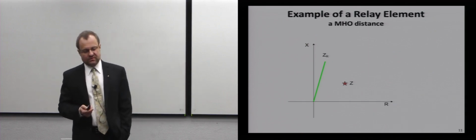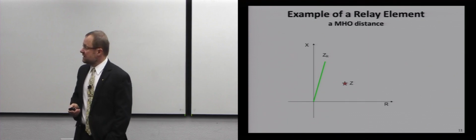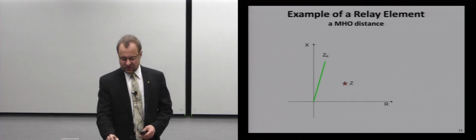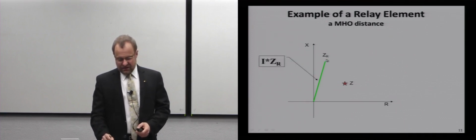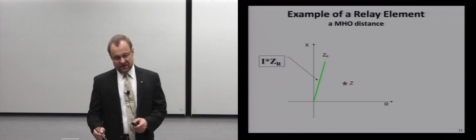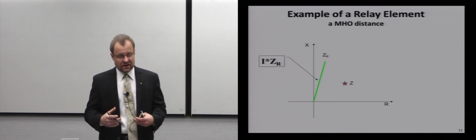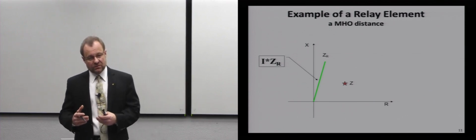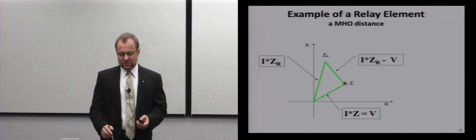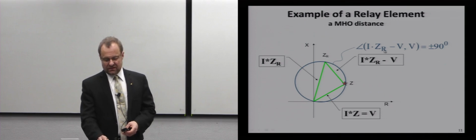So when you look back at the principles of, say, a mho distance function, you know that you have an impedance reach. You want to reach up to this point, right? And you know one thing: if you build a term, current times the replica impedance, where I is the current that I am measuring right now and ZR is the setting, the point I would like to reach to, then mathematically, to draw a circle, you check the angle between this magic expression, I times ZR minus V, and V, and compare it with 90 degrees. An angle less than 90 degrees would be the inside of that circle. This is where I'm going to trip. And an angle greater than 90 degrees is the outside of that circle. This is where I want to block.